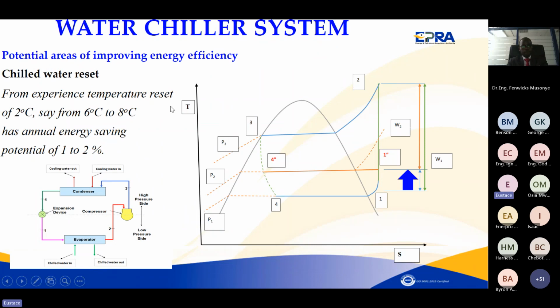The other measure is you can try to check the set points. If you find that you don't require very low temperatures, you can try, at the evaporator, to make them go as high as possible. Probably if you require temperatures between 6 and 8, why do you go down to 2? If this one can do well, it's okay.